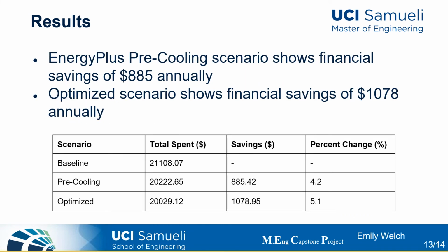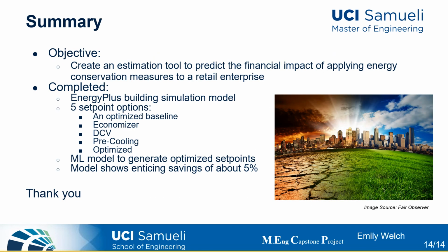The retail store that we trained our models on spends an average of $21,100 annually on their HVAC system. By employing a pre-cooling scenario, the store could save an estimated $885 annually. But if we employ our optimized set points that were derived from our machine learning, we can estimate savings of over $1,000. We have created and analyzed the effect of 5 different scenarios a building can implement by creating an optimized baseline, altering the performance of the economizers and DCV, by employing pre-cooling, and by generating an optimized schedule using a combination of baseline and pre-cooling schedules.